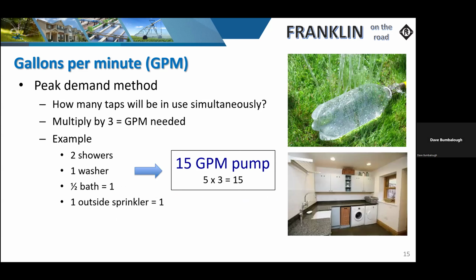Now, the peak demand method is a little different way of looking at sizing a system. The way it works is you look at what appliances in there could be running at the same time, and then you're going to multiply it by 3. So as we look in this example, and again, this is a guess. I don't like doing this because it opens up too many what ifs. Like a shower, we could take in consideration both showers are going. There's a dishwasher and maybe something in the sink and or some kind of use there in the half bath.